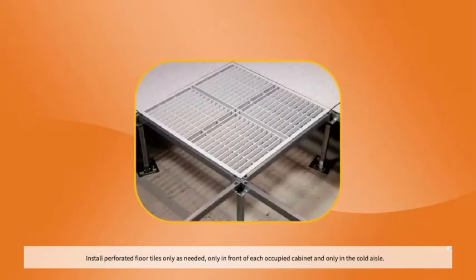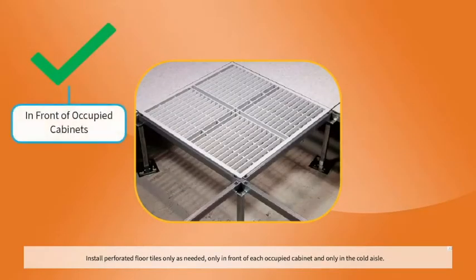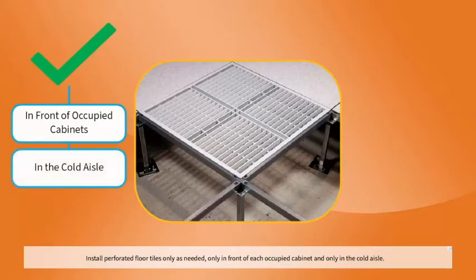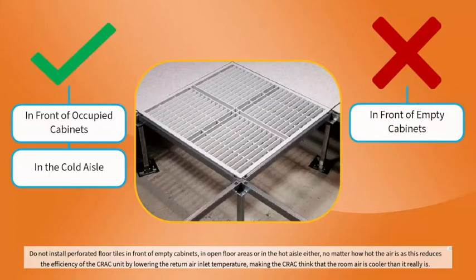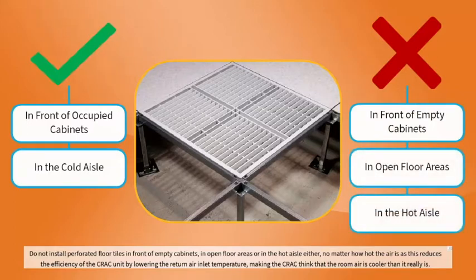Install perforated floor tiles only as needed — only in front of each occupied cabinet and only in the cold aisle. Do not install perforated floor tiles in front of empty cabinets, in open floor areas, or in the hot aisle either.